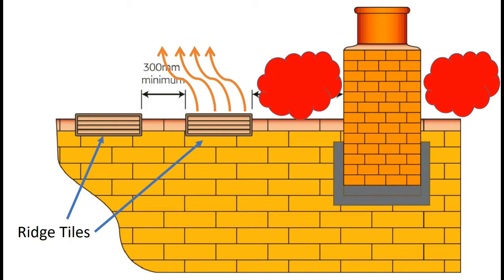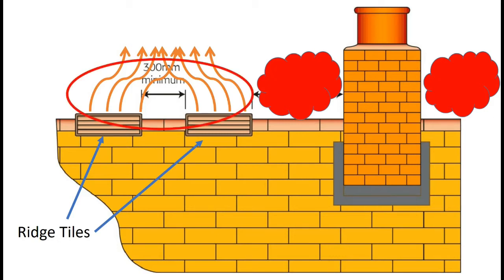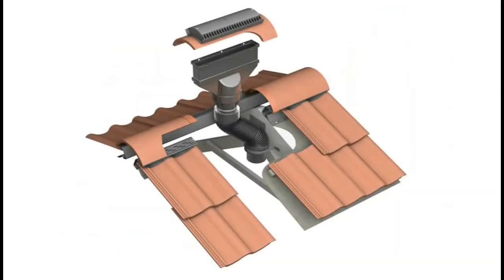Ridge terminals, when they are working, let hot gases out from the top of them. If you place them too close together — nearer than 300 millimetres apart — then the likelihood is that the hot gases will interfere with each other and create another unusual pressure zone within the red circle. Any unusual pressure zone is going to be a problem to the operation of the flue. This is just an exploded view of a ridge terminal to remind you what it looks like in real life.